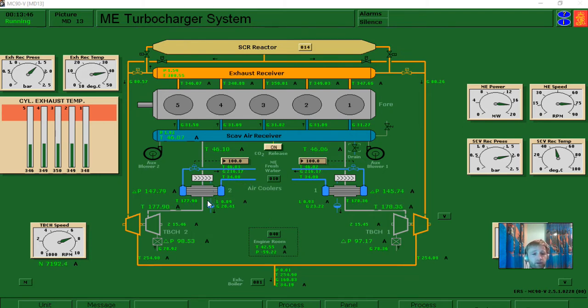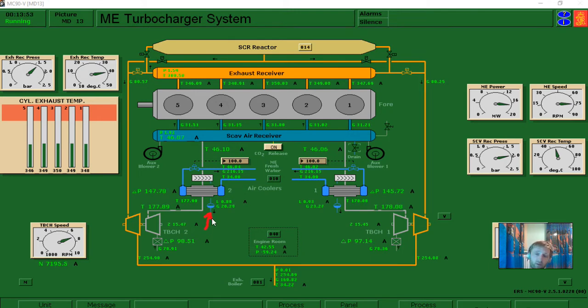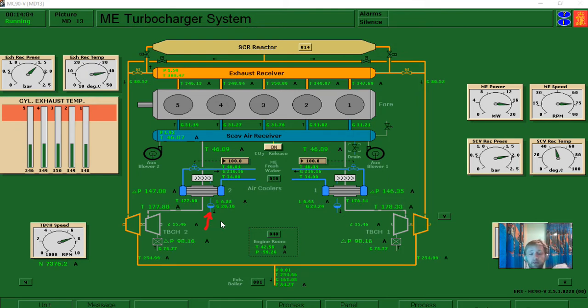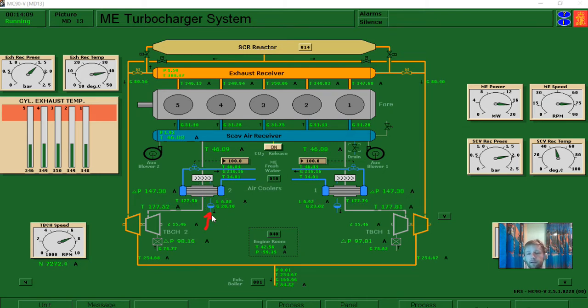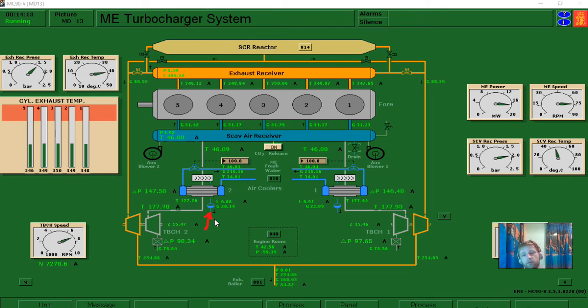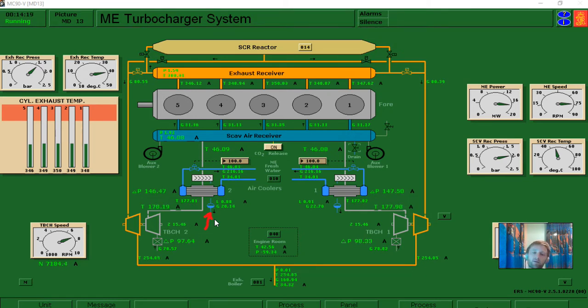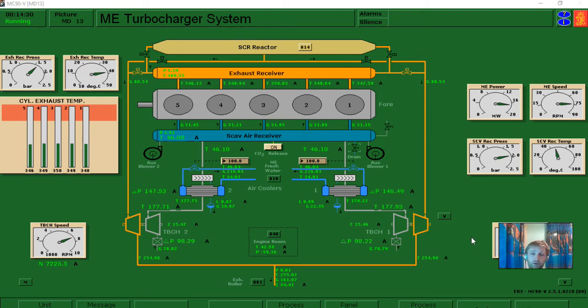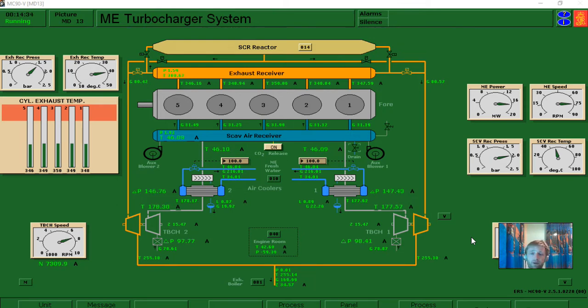Very very close monitoring must be done from the side glasses which are down below, and there is a label and note that shows that these kind of side glasses must be kept clean and monitored. The condensate from the air cooler goes to bilge holding tank and there is not any restriction of that flow. Also the water does not enter the space of the scavenging and the cylinder itself. As we know, water is the worst component for the engine due to the mixture of the fuels and the oils. We will avoid the formulation of oxides inside our engine and we will reduce also the possibility of wear.